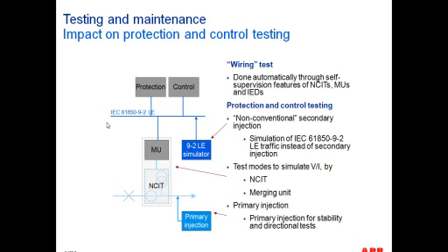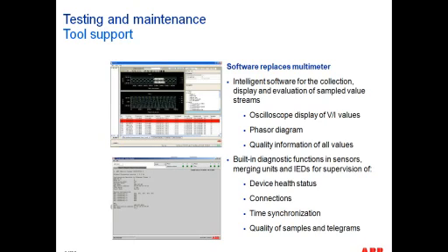It is also important to mention that the 9-2 LE implementation guidelines offer a test bit in such a way that if, let's say, you use your tester to inject sample values onto the network, those sample values will have a test tag, and then it is based on the behavior of the device from the manufacturer how it would react to it. But that is something that could be used to indicate that those sample values are coming from a test device, so that the devices, if they're told to do so, should not react to that information. So that's something that's quite important to take into consideration for the maintainability of the system.